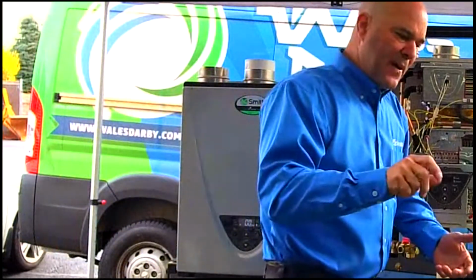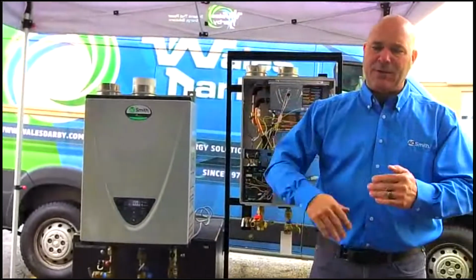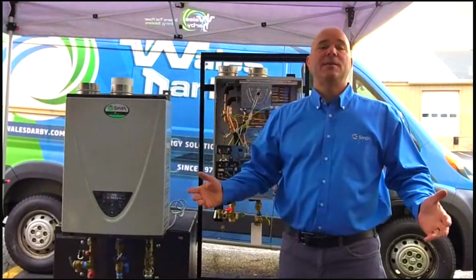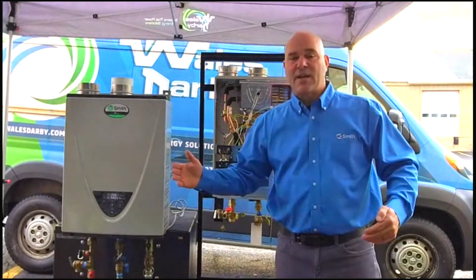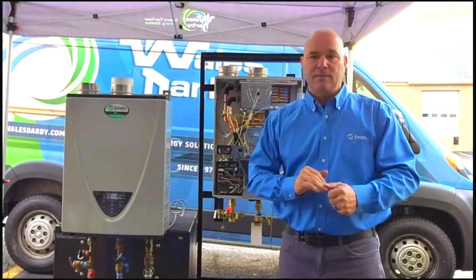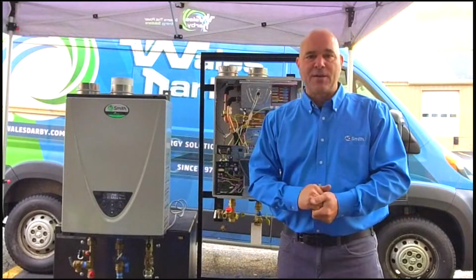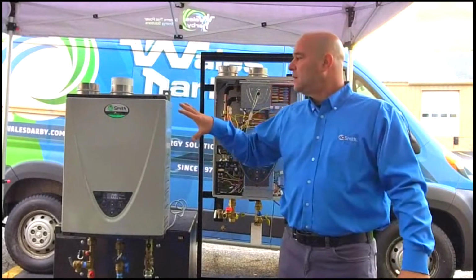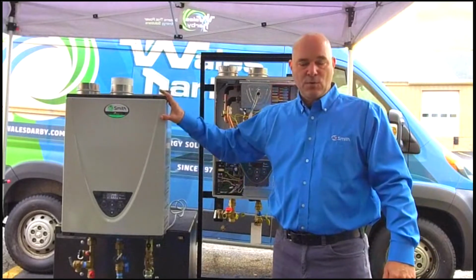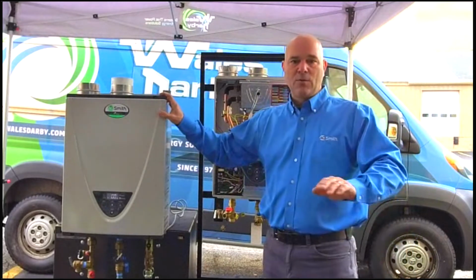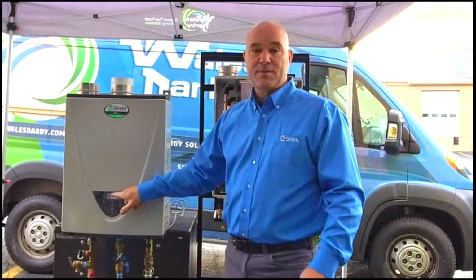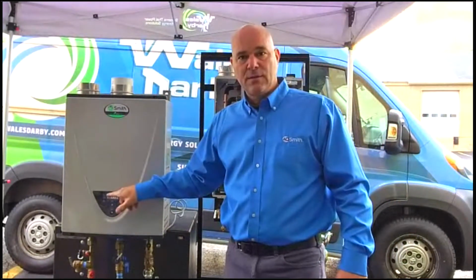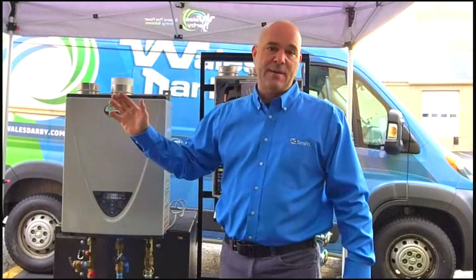If I'm drawing it off at a rate that the unit can recover, I'm fine. But if I try to do 5 showers in a row out of a 40-gallon water heater, the last 2 people are getting cold showers, right? Tankless water heater, this water heater right here, will always deliver the target temperature that you're looking for. So we will give you that temperature forever.